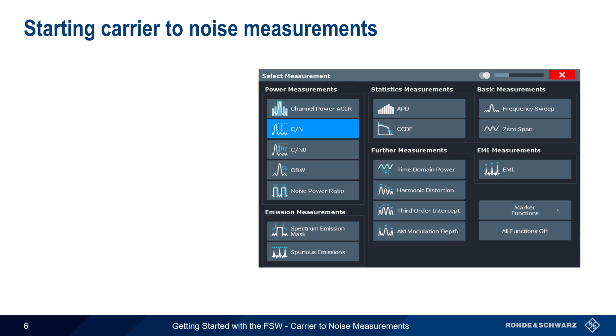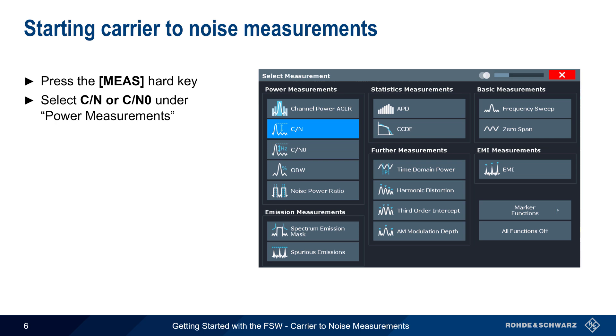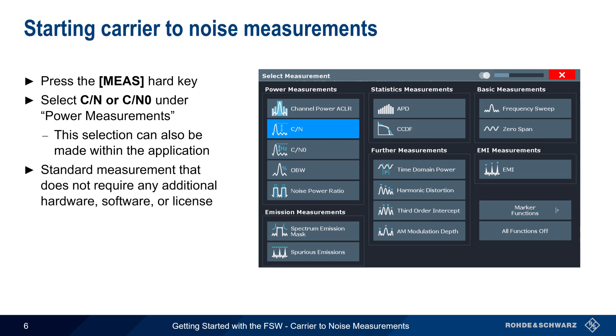To make Carrier-to-Noise measurements on the FSW, press the Measure Hard key and then select either Carrier-to-Noise or Carrier-to-Noise Density from the list of available power measurements. Note that this selection can also be made within the application itself. Carrier-to-Noise is a standard spectrum measurement and does not require any additional hardware, software, or license code.